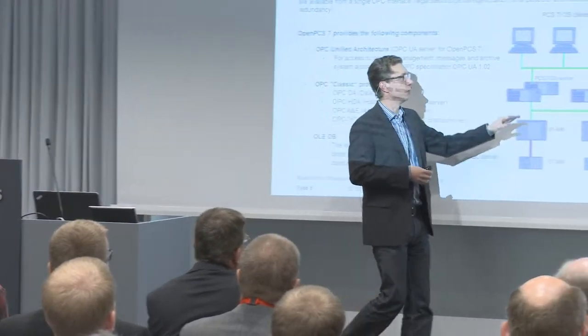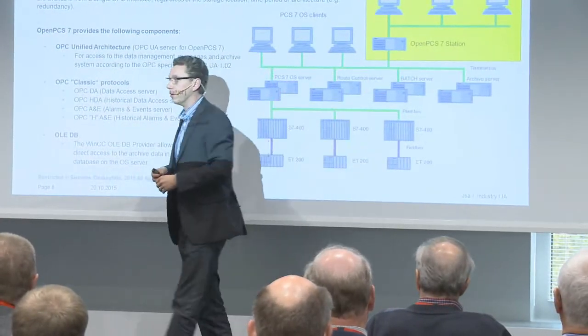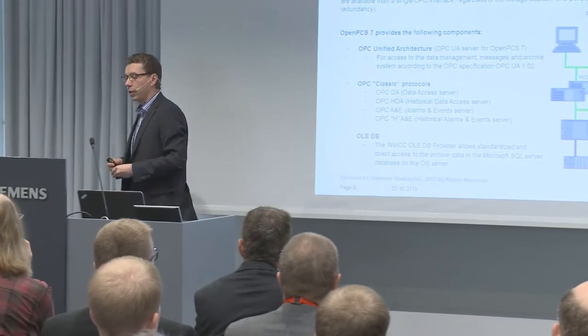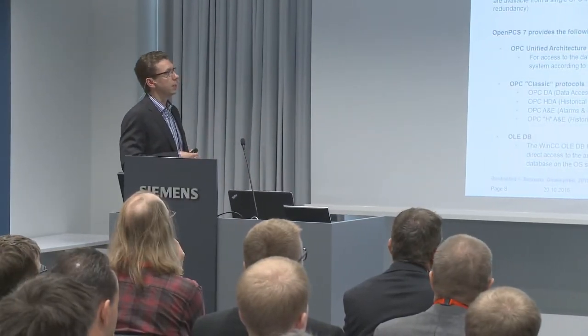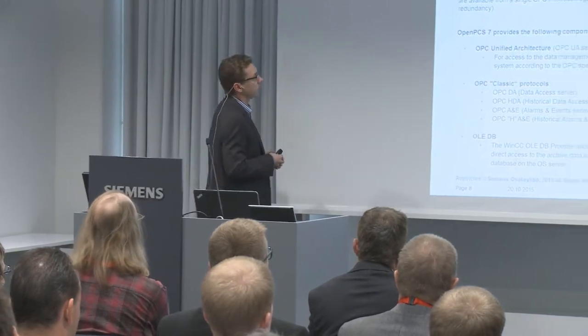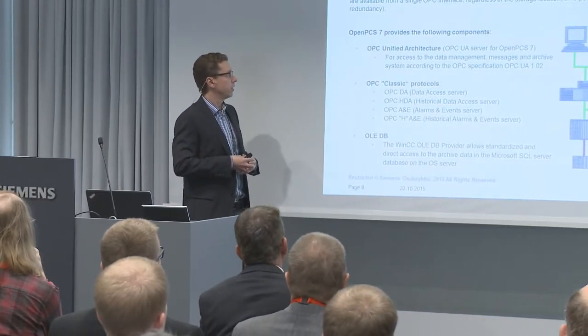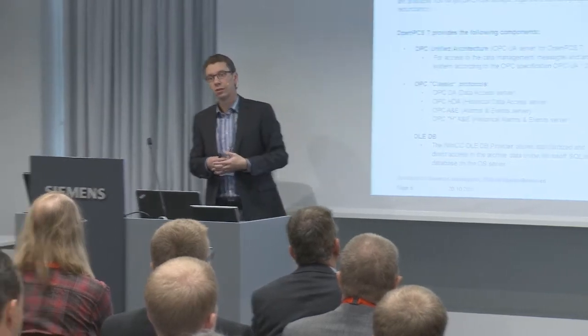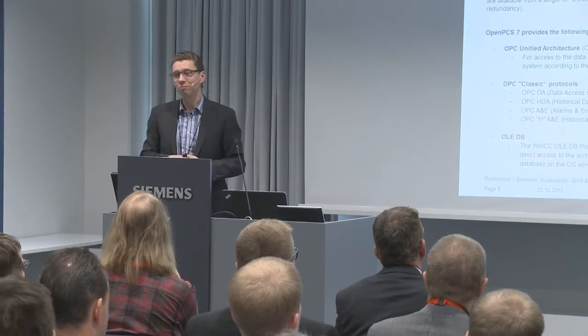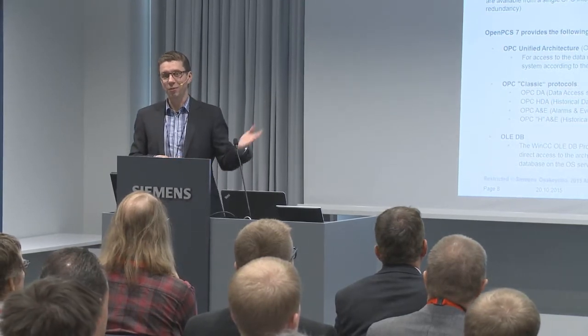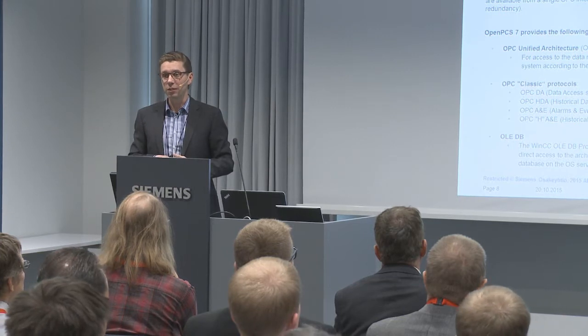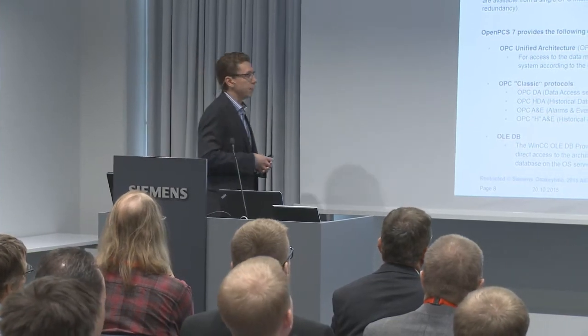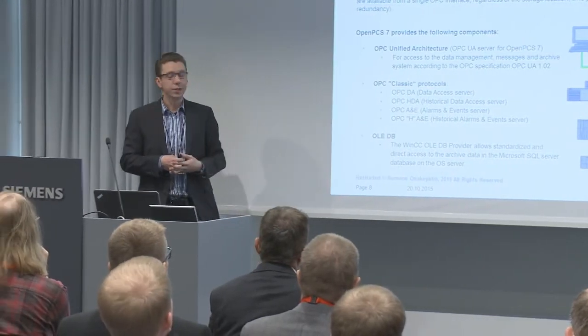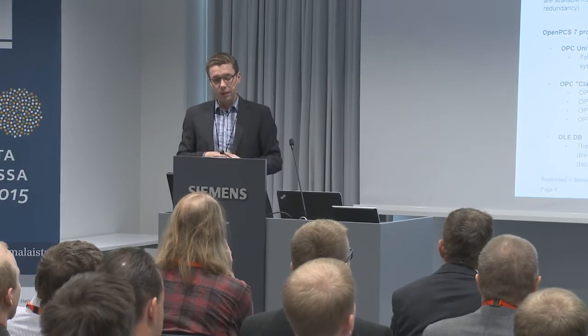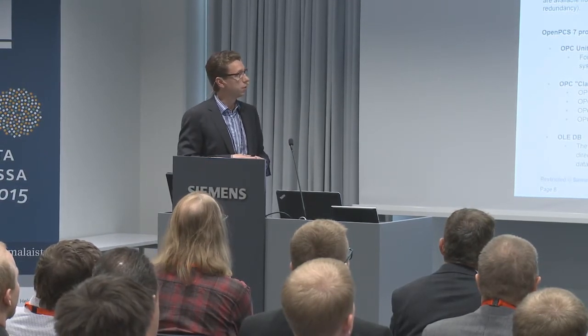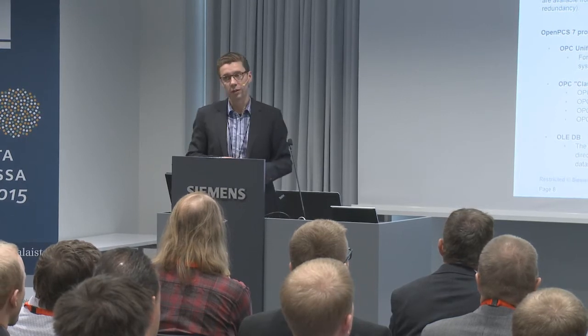You typically put that between an automation firewall, so you can separate it from the process network. Via the open PCS7 station you then have, for example, OPC UA connectivity, or also classical OPC connections, but nowadays we prefer UA for the sake of security, as also mentioned in the morning presentations. Also there, if needed, we still have OLE DB direct connectivity to a database, but with OPC UA the security is better and it's easier to handle from a security standpoint.